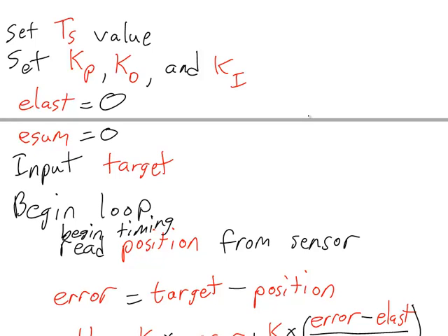What you would do is you would start out by setting only KP. And you would put in a value for KP and then run your positioning program and watch the response of the manipulator. You would want to continue to increase KP until there was too much overshoot, more overshoot than is acceptable.